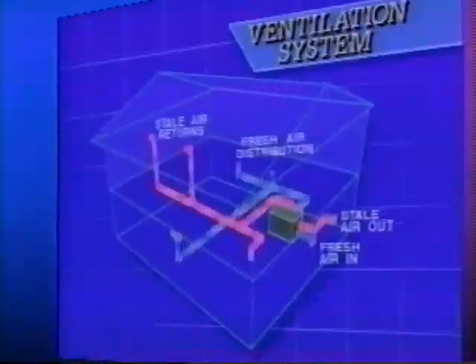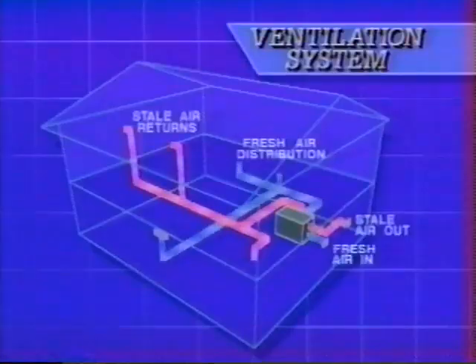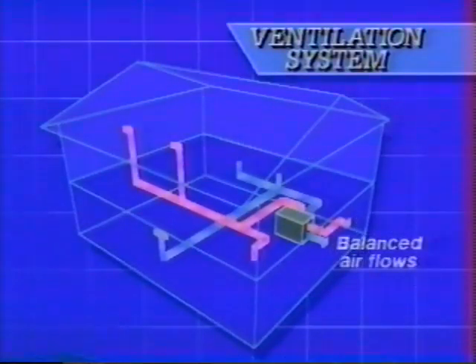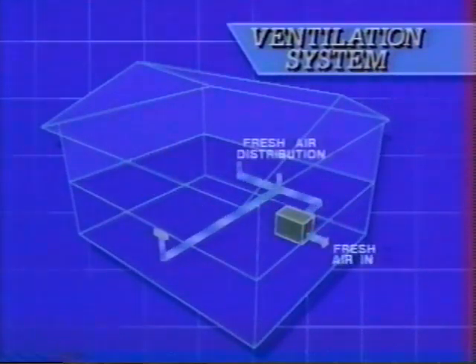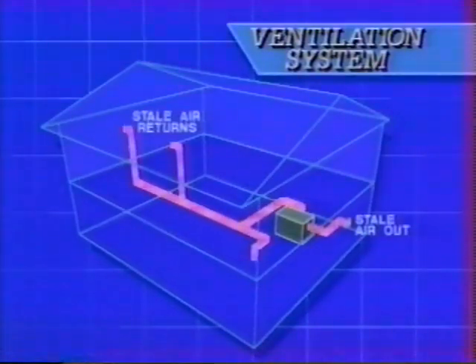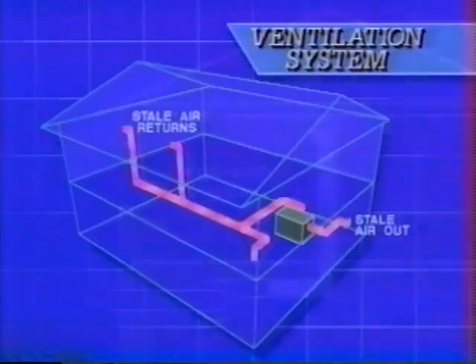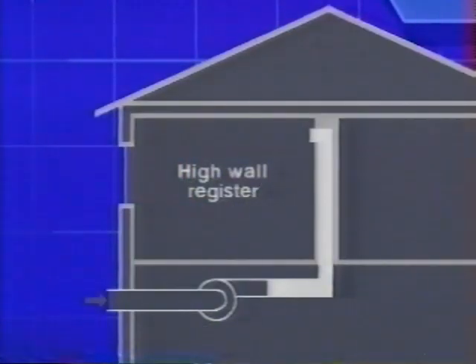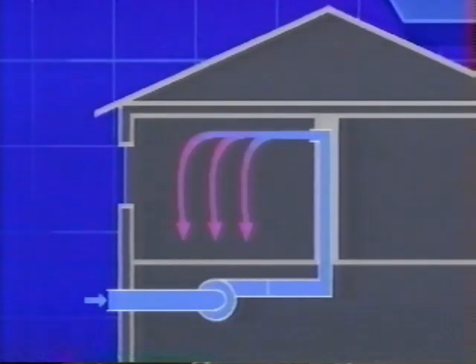But I don't want to disappoint David, and I know that at this time in the program we usually have a review, so here it is. Ventilation is an important requirement of the Better Built House. A mechanical ventilation system must be properly sized to meet the fresh air requirements of the house and must be designed to provide fresh outside air to each room of the house. The ventilation system must be capable of exhausting stale air, household pollutants, and humidity from those areas in the house where they are produced. Finally, the ventilation system must be designed to supply the fresh air to the homeowners in a comfortable manner.